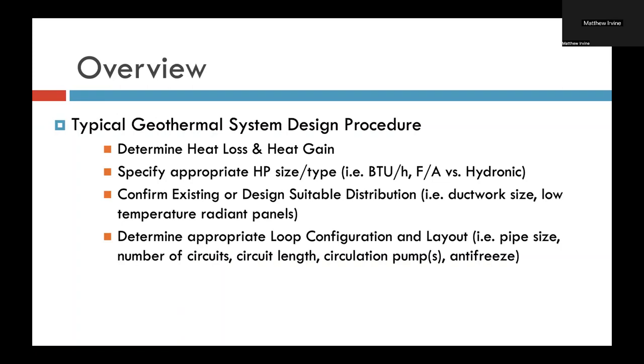So the geothermal system design procedure is: determine the heat loss and heat gain. Calculate how many BTUs per hour you need to provide to the house in the wintertime on the coldest day, and then how many BTUs per hour you need to remove from the house on the hottest day. Based on these calculations, you would specify the appropriate heat pump size and type. So how many BTUs per hour are you looking to provide or remove?